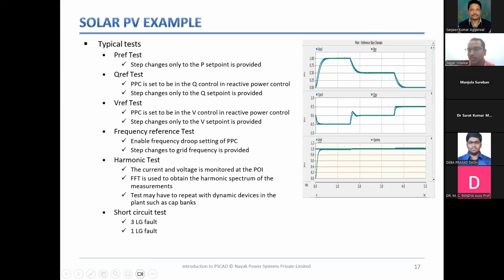Then you have to check whether the rate at which this power changes matches with what the grid code asks you to do, and then take out the results and report it nicely into a document to confirm that the plant meets the requirements. Now, that forms your active power step changes. Similarly, you have your reactive power test, where you will give certain reactive power set points to the PPC, and then you will check whether the responses are met or not.